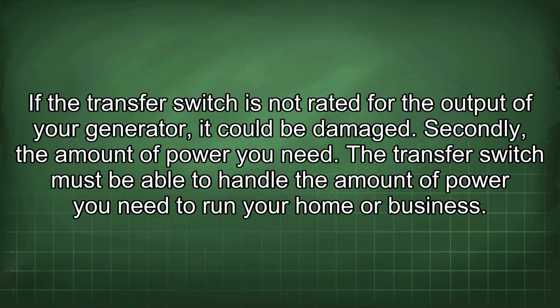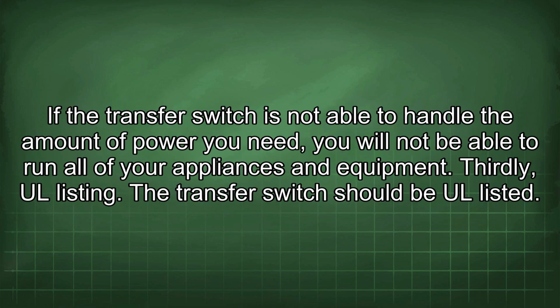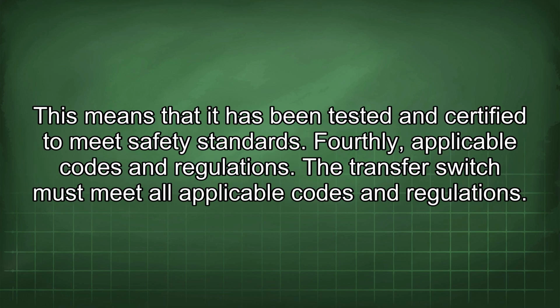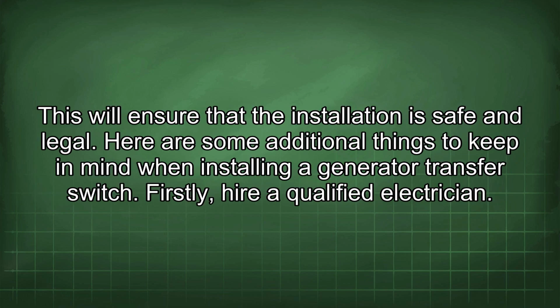Secondly, the amount of power you need. The transfer switch must be able to handle the amount of power you need to run your home or business. If the transfer switch is not able to handle the amount of power you need, you will not be able to run all of your appliances and equipment. Thirdly, UL listing. The transfer switch should be UL listed. This means that it has been tested and certified to meet safety standards. Fourthly, applicable codes and regulations. The transfer switch must meet all applicable codes and regulations. This will ensure that the installation is safe and legal.